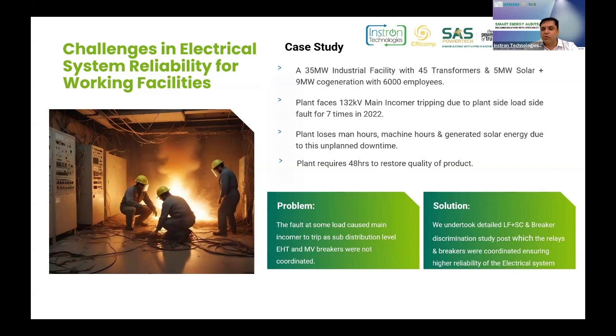So here, the problem was that a fault at some load caused the main incomer to trip, as sub-distribution level breakers, EHT and MV breakers, were not coordinated. It was a very small and simple exercise. The solution was that we undertook a detailed load flow and short circuit study and did a breaker discrimination study, after which these relays and breakers were coordinated, ensuring higher reliability of the electrical system. And I can vouch, and I can be very proud to say, that after this, they have never faced any main incomer tripping caused by their plant load and faults.